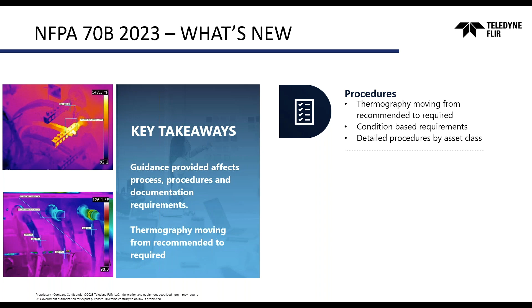Within the procedure side, we might mention that moving from recommended to required. There are also some condition-based requirements, with three different categories that NFPA references. Category 1 is equipment that is in a state of good repair and does not have any material issues relative to failures. That condition 1 asset is required, at a minimum, to be inspected annually. Moving down the ladder to category 3, where the condition is not good or is in a failing state, the inspection requirements increase to every 6 months. Additionally, within category 2, if you did not perform your annual inspection, you need to perform that inspection every 6 months until you're brought back to current. And then the detailed procedures by asset class are all included in the documentation.